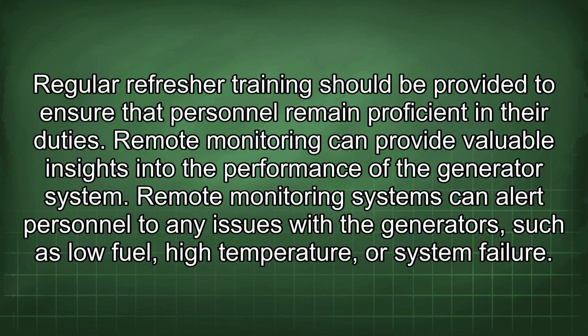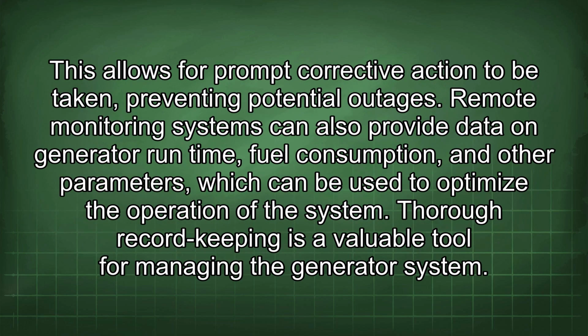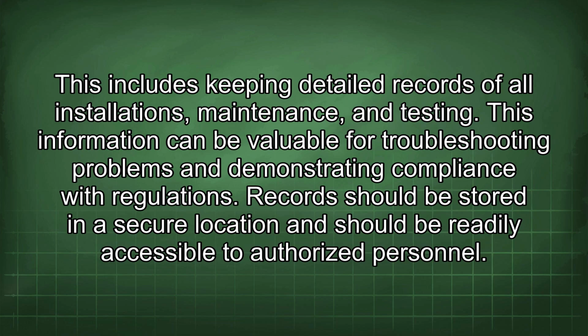Remote monitoring can provide valuable insights into the performance of the generator system. Remote monitoring systems can alert personnel to any issues with the generators, such as low fuel, high temperature, or system failure. This allows for prompt corrective action to be taken, preventing potential outages. Remote monitoring systems can also provide data on generator runtime, fuel consumption, and other parameters, which can be used to optimize the operation of the system. Thorough record keeping is a valuable tool for managing the generator system. This includes keeping detailed records of all installations, maintenance, and testing. This information can be valuable for troubleshooting problems and demonstrating compliance with regulations. Records should be stored in a secure location and should be readily accessible to authorized personnel.